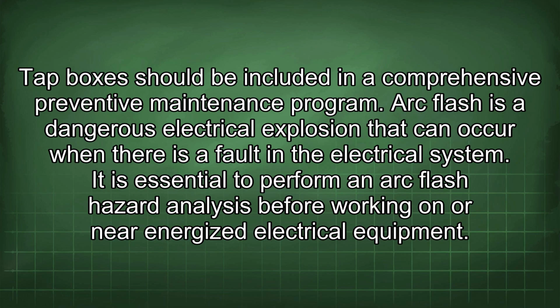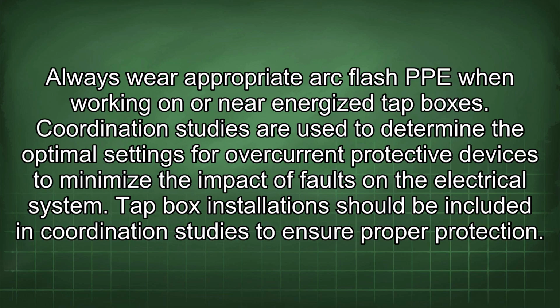Arc flash is a dangerous electrical explosion that can occur when there is a fault in the electrical system. It is essential to perform an arc flash hazard analysis before working on or near energized electrical equipment. Always wear appropriate arc flash PPE when working on or near energized tap boxes. Coordination studies are used to determine the optimal settings for overcurrent protective devices to minimize the impact of faults on the electrical system. Tap box installation should be included in coordination studies to ensure proper protection.